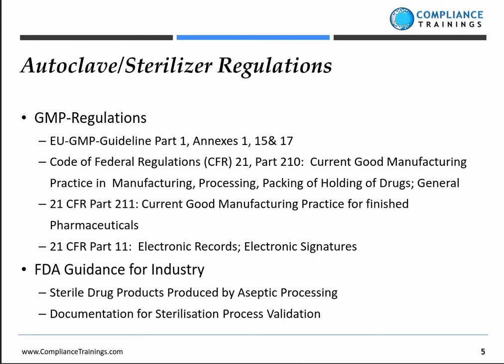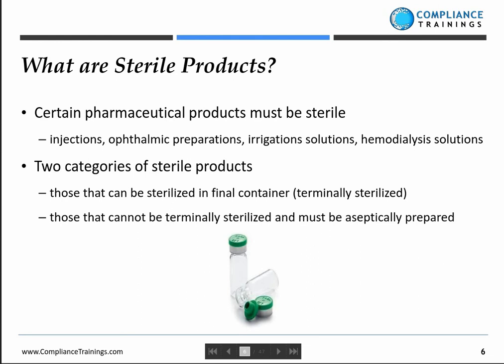Some autoclave and sterilizer regulations: I found some GMP regulations that are worth noting. You can take a look at the EU GMP Guideline Part 1, Annexes 1, 15, and 17 — they have quite a lengthy list of regulations when it comes to autoclave and sterilizer regulations, as they do in the CFR Parts 210, 211, and even Part 11 when it comes to autoclaves and electronic records and signatures. And of course, the FDA has two great guidances for our industry: the sterile drug product produced by aseptic processing, and also the documentation for the sterilization process validation, which is definitely a good read.